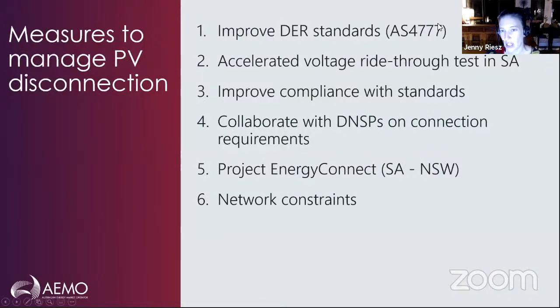There's a bunch of work underway to improve the way that we're able to handle this. So we're working to improve Australian standards which apply to these small-scale rooftop systems to make sure that they've got appropriate testing for voltage ride-through behaviour, because very soon our grid will reach the point where if we keep installing PV with this behaviour, we'll no longer be able to supply enough frequency reserves to manage the extremely large contingency sizes. We've also accelerated the take-up of that voltage ride-through testing in the South Australian region because we do have a particularly large amount of PV in that region. We're working to improve compliance with those standards.